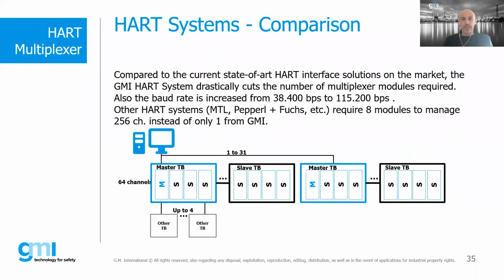Market comparison. We have a single slide for this, and we have seen that our multiplexer manages up to 256 channels, while others in the market are limited to 32. And for every 32 you need a multiplexer, so maybe you have a master and a slave. In our architecture, we only use single multiplexers that can be considered masters, for 256 channels. So the overall cost for the application is considerably lower. Of course, this will affect the refresh time for your data on your PC, but that is not critical in HART communication, in HART management.